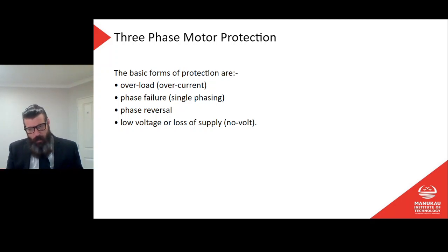That's weird. If you have a production line, let's say big motors that are dragging logs down a production line in a milling operation, so the logs will then be debarked and cut into slices and so on and so forth. Imagine the carnage that would happen if I reversed all the motors in something like that, and we had logs getting pushed back up the chute rather than coming down the way they're supposed to. It could be very, very dangerous. So in those types of cases, we need to have some sort of protection against phase reversal. And we want low voltage or loss of supply protection as well.